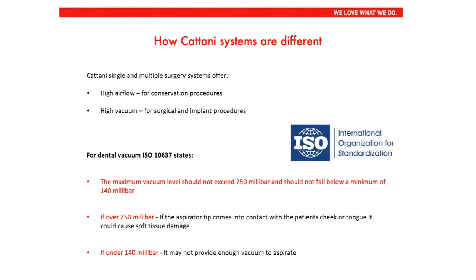How Cattani systems are different. Cattani single and multiple surgery systems offer high airflow for your conservation procedures and high vacuum for your surgical and implant procedures. For dental vacuum, ISO 10637 states the maximum vacuum level should not exceed 250 millibar and should not fall below a minimum of 140 millibar. If over 250 millibar, if the aspirator tip comes into contact with the patient's cheek or tongue, it could cause soft tissue damage. If under 140 millibar, it may not provide enough vacuum to aspirate.